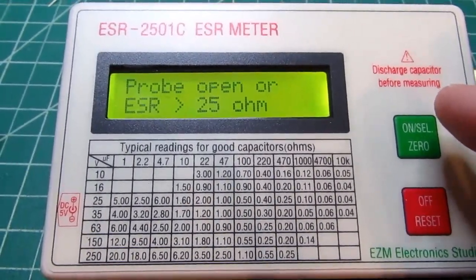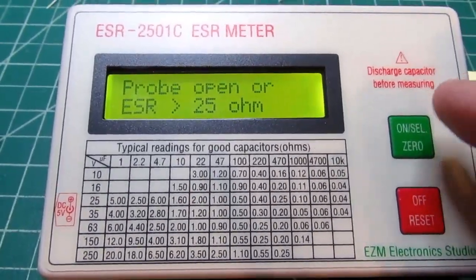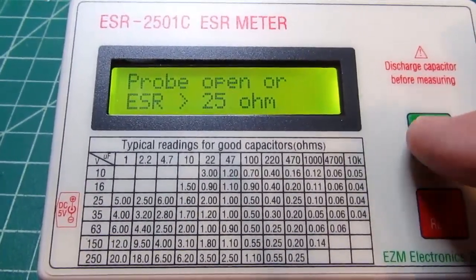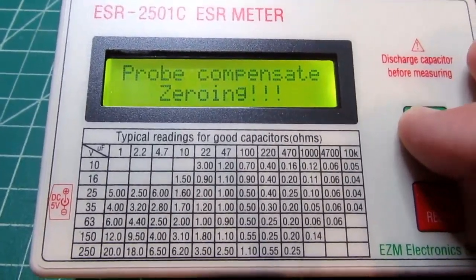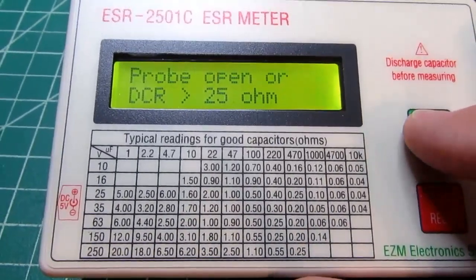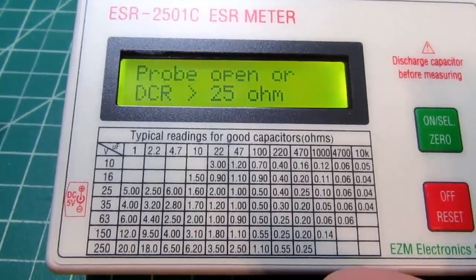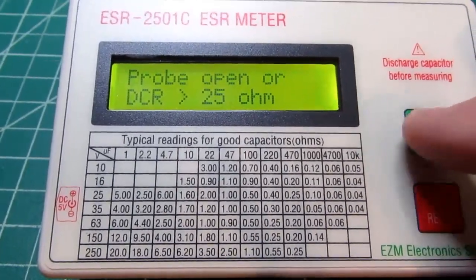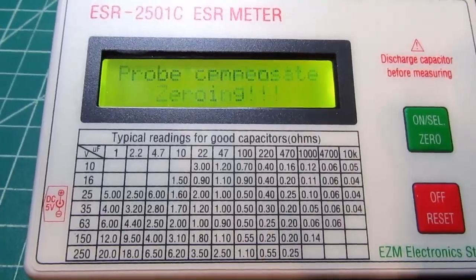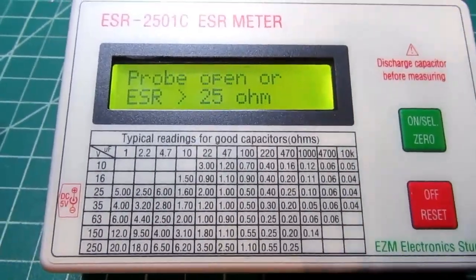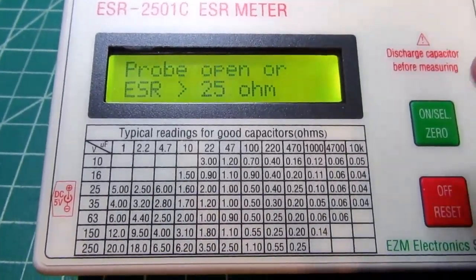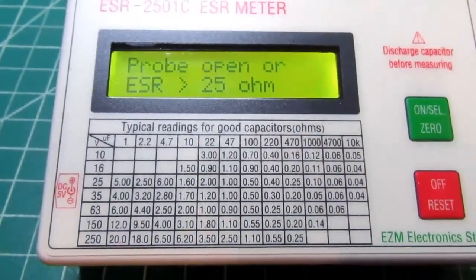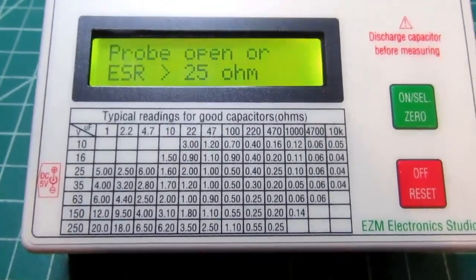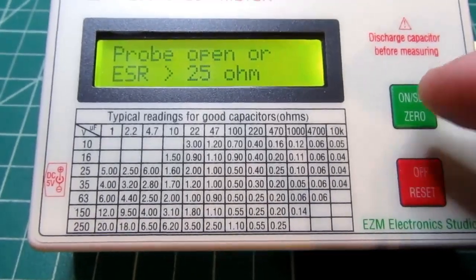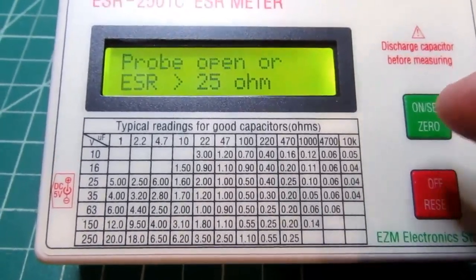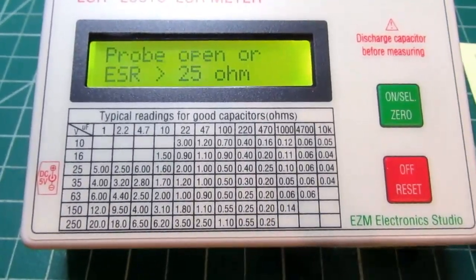If somebody else knows the trick to this... I tried it with a 1 second hold, a 2 second hold. I'm sitting here in ESR mode, I push it down for 2 seconds, what happens? It changed to DCR mode. What if I just push it for 1 second? It stayed in DCR mode, but it did not re-zero. 1 second, it changed to ESR. I know I have caught it switching or re-zeroing without changing modes, but I don't know what I did to make that happen. Supposedly it's possible. Anyway, the worst that happens is if you zero it thinking it needs zeroing and it changes to the other mode, you just repeat it and it'll be back in the mode you want.